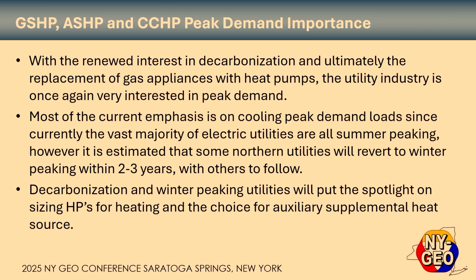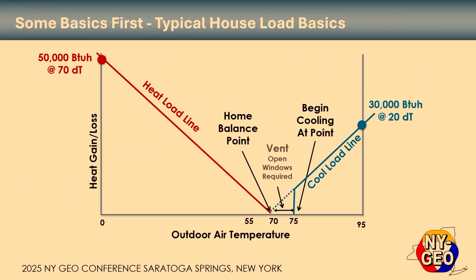So decarb and winter peaking utilities will put the spotlight on sizing the heat pumps for heating and the choice for auxiliary supplemental. All of those things are going to be super important in the future. I can't really talk about peak demand unless you start talking about the sizing of the equipment. And so you'll hear me talk about that a lot in here because traditionally heat pumps, especially air source heat pumps, have not been sized for heating. They've been sized for cooling, and then you let whatever happens on the heating side happen. But those are all going to be things of the past, I think, in the future.